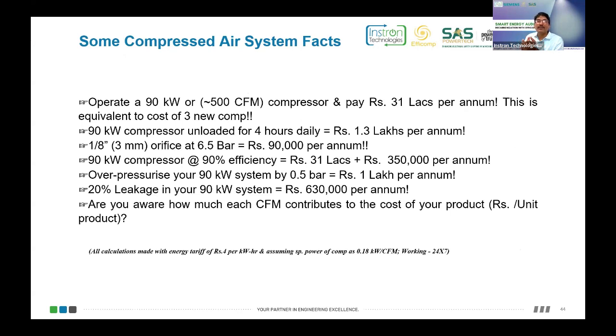Generally, if you are not sitting in our office, we don't run the AC. Similarly, when we are not using compressed air in the plant, during that time also the compressor runs on unload mode. So running a compressor only in unload mode for 4 hours a day, when the compressor is not delivering anything but only the motor is running, 1.3 lakh rupees will just be gone, only running in unload mode.